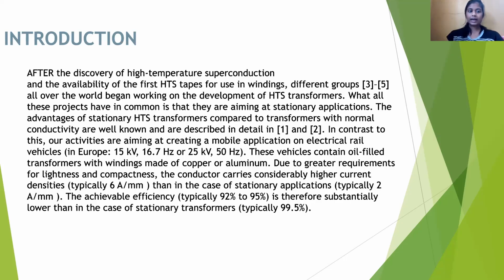In contrast to this, our activities are aiming at creating a mobile application on electrical rail vehicles. In Europe, the supply is 15 kV at 16.7 Hz or 25 kV at 50 Hz. These vehicles contain oil-filled transformers with windings made of copper or aluminium. Due to greater requirements for lightness and compactness, the conductor carries considerably higher current densities, typically 6, than in the case of stationary applications, typically 2. The achievable efficiency, typically 92% to 95%, is therefore substantially lower than in the case of stationary transformers, typically 99.5%.